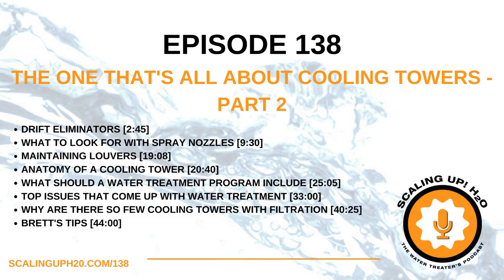At this specific site, what we found is that the leaks or weeping on that tower were only in two corners of each cell. It was a 2-cell cooling tower, and when you walked up, the leaks were at the two corners of each of the cells that face each other. What this water treatment company had been doing is dumping a granular DMH biocide into that basin, just for a little slug feed, a little shock feed every once in a while.